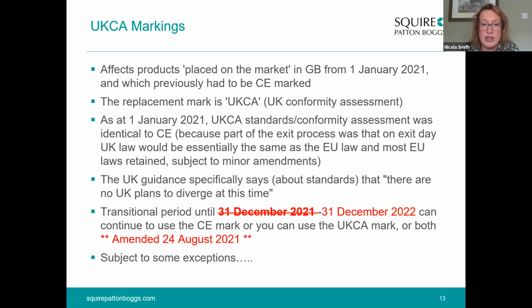In terms of the conformity assessment process itself, that varies depending on the type of product. For many products, there will be a declaration of conformity by a process of self-assessment, so declaring that the product conforms because you've reviewed the standards and ensured, as a manufacturer or a representative of the manufacturer, that the product complies. But generally, for some products that need higher and stricter safety standards, you might need something called a notified body to be involved. There are lots of notified bodies around, companies like BSI or TUV or SGS, where the notified body has to actually assess the product or the design and manufacturing standards to confirm that it conforms with the requirements.